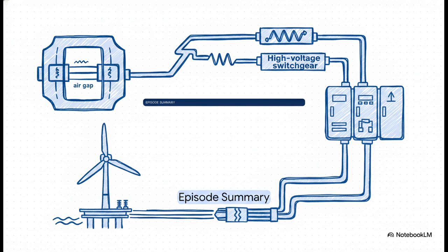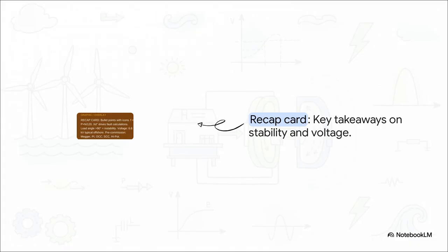Okay, let's bring all of this theoretical and practical knowledge together for a quick recap. We have covered a tremendous amount of ground today, from the microscopic air gap all the way to the high-voltage switchgear. Just remember the key takeaways. Subtransient reactance is what drives your immediate fault calcs. A load angle creeping over 90 degrees will cause massive instability. 6.6 kilovolts is your standard offshore voltage for anything over 1 MVA. It's the absolute linchpin that allows those massive generators to deliver power without needing impossibly huge cables. And of course, always follow that strict pre-commissioning sequence.